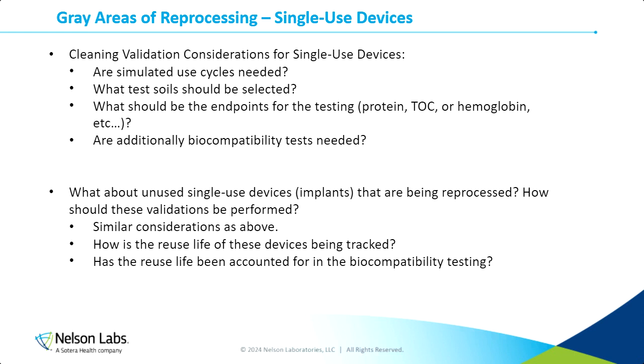Now, for us, we would most likely say that simulated use cycles are not needed because the devices are not being reused. So we don't need to account for any accumulation of soil over repeated use because they're just being cleaned and sterilized once and then used. So those wouldn't be required. Test soils, they haven't been used on a patient yet. So using a blood test soil may not be appropriate, or a test soil that mimics the use of the device probably wouldn't be appropriate. And you would want to use one that mimics how the device is presented to the user prior to cleaning. So maybe something that mimics skin contact.